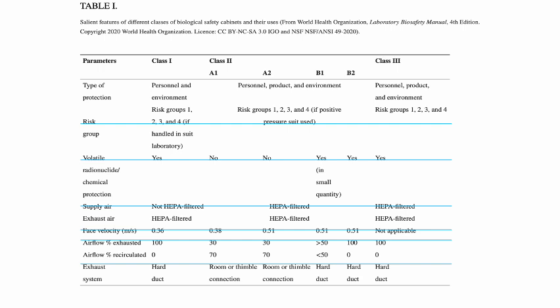While the class 1, B1, B2, and class 3 can provide protection against toxic substances, because their exhaust system is hard ducted. Now, in terms of the supplied and exhaust air, is it HEPA filtered or not? The only biosafety class that does not supply HEPA filtered air is class 1. The rest, both supplied air and exhaust air, are HEPA filtered.